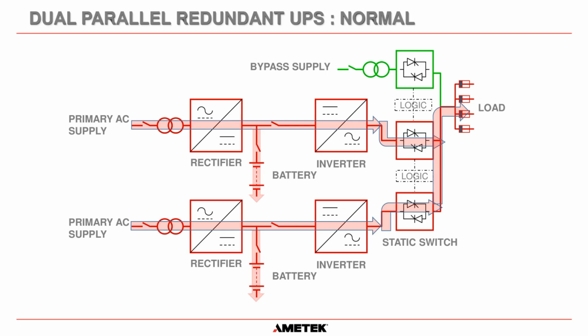But in normal operation, once again, we use red for power flow and green for ready if necessary. So the power flow: both UPSs are flowing power from their chargers through the inverter, through the static switch, and then they are connected physically in parallel. So if it's a single phase UPS, the hot will be connected together and the neutrals will be connected together, and then that will go out to the load circuits.